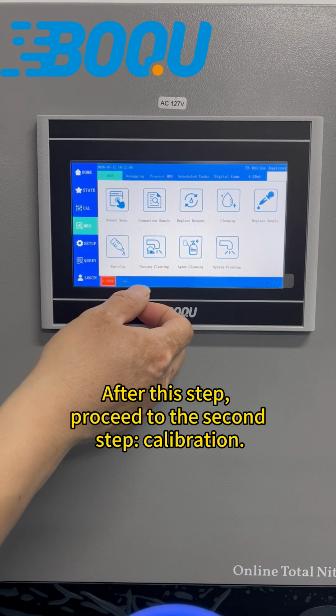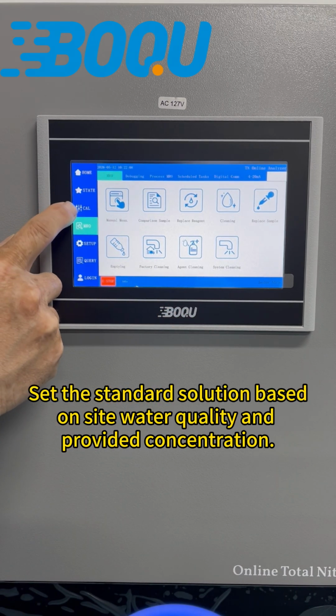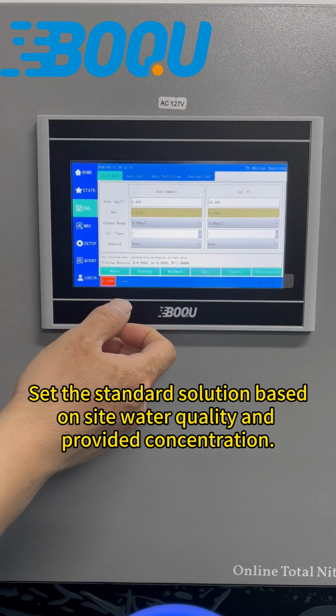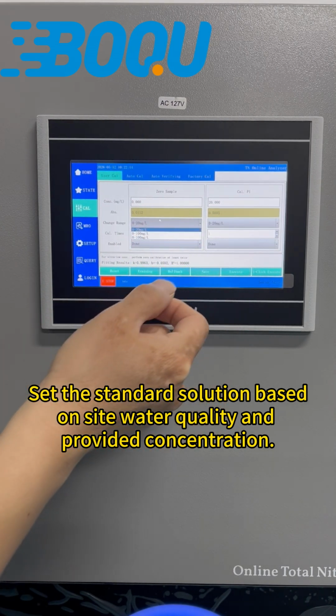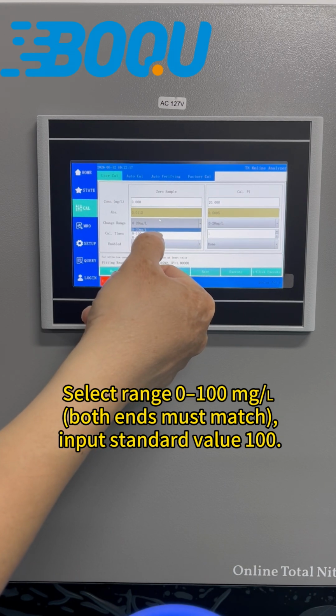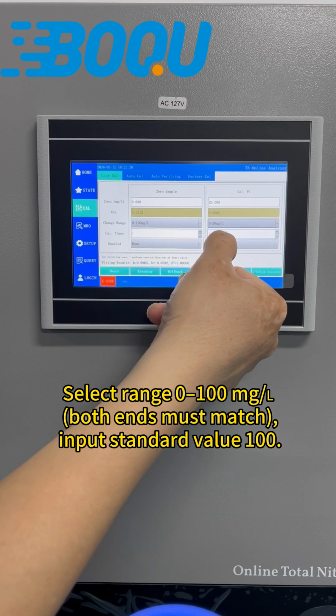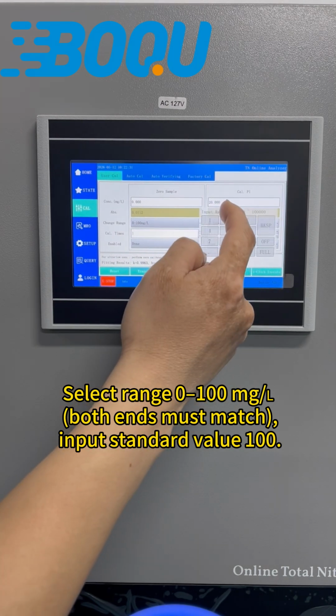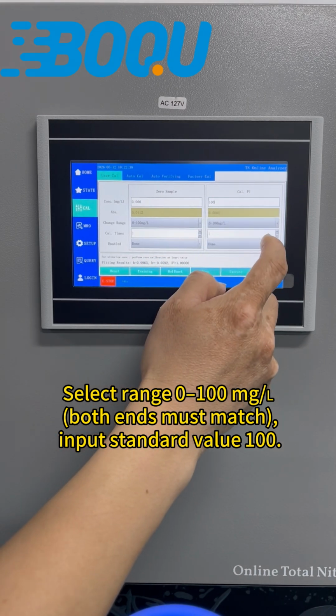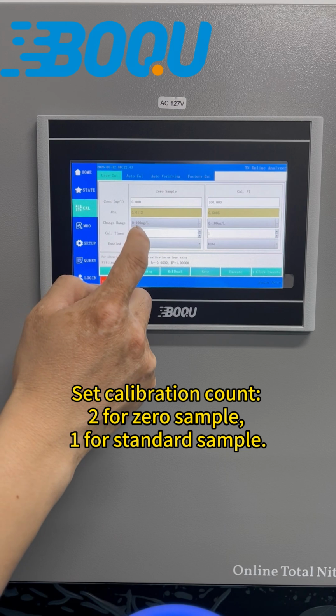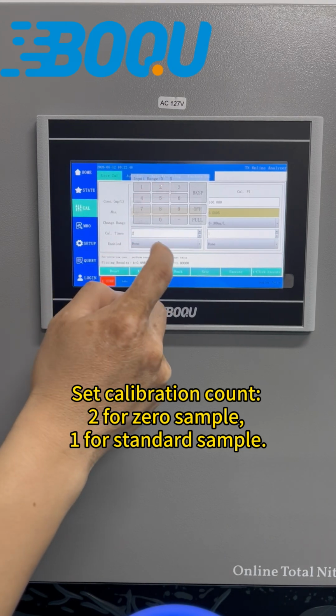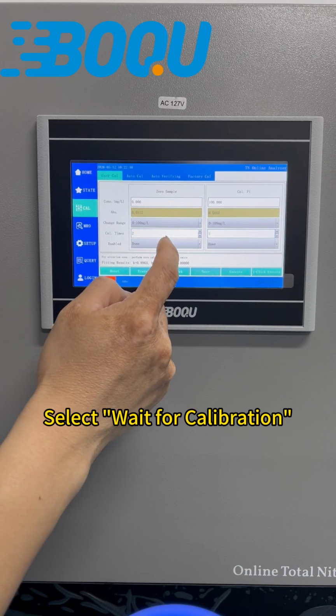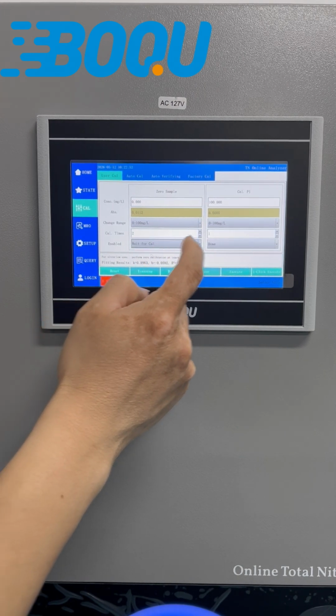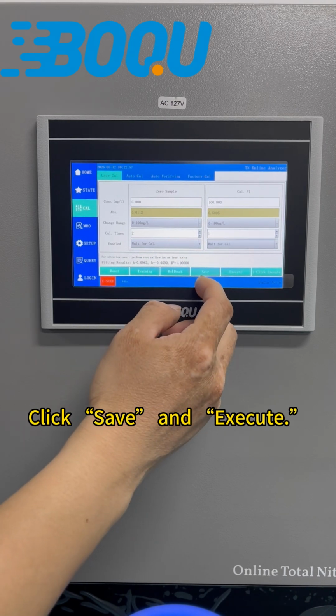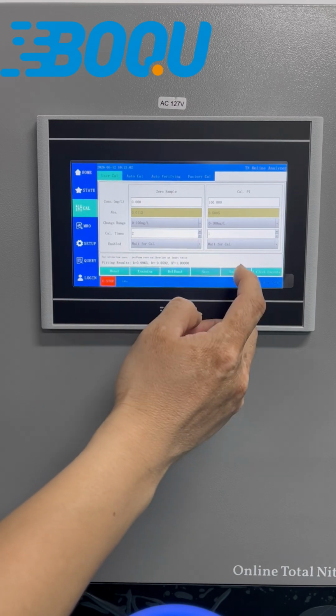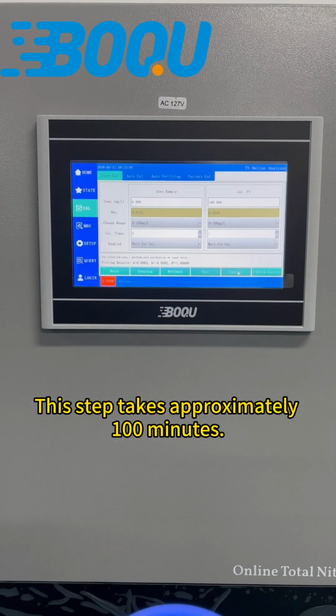After this step, proceed to the second step, calibration. Set the standard solution based on site water quality and provided concentration. Select range 0 to 100 milligrams per liter. Both ends must match. Input standard value 100. Set calibration count 2 for 0 sample, 1 for standard sample. Select Wait for calibration. Click Save and Execute. This step takes approximately 100 minutes.